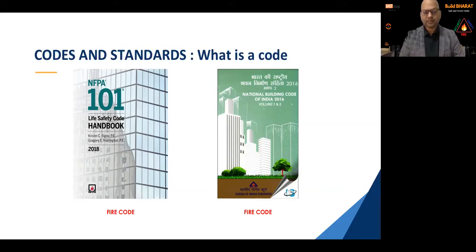We all know that NBC, National Building Code in India, is the building code available for fire - even Part 4, which is specifically dedicated for fire code, for fire systems, fire and life safety systems. That's a code. Internationally, or as a global practice, NFPA 101 is the life safety code for that matter. These are the codes which give you answers in terms of general requirements. So specifically when it comes to fire and life safety, these are the two Bibles, and you can find an answer. Any occupancy, any facility that you have, most of the questions will get answered.